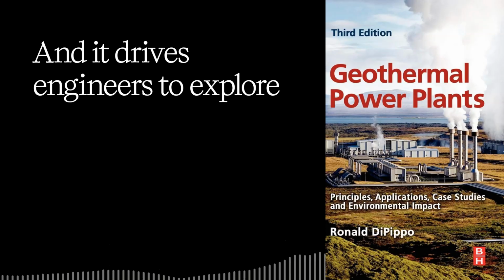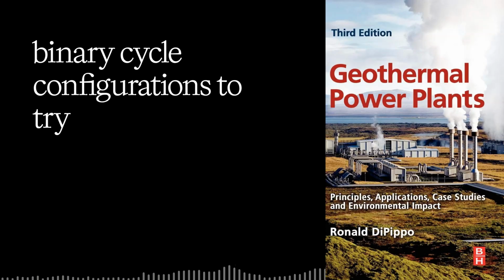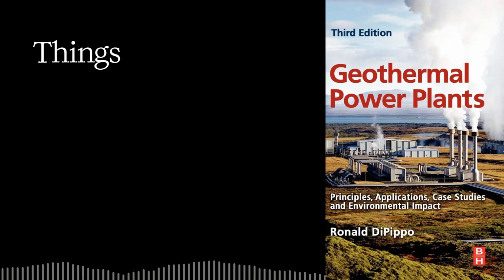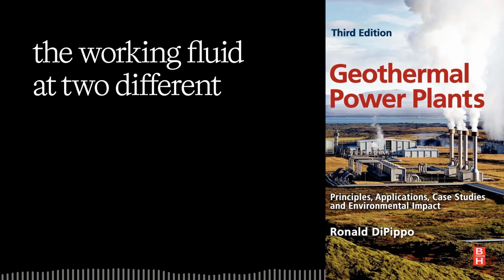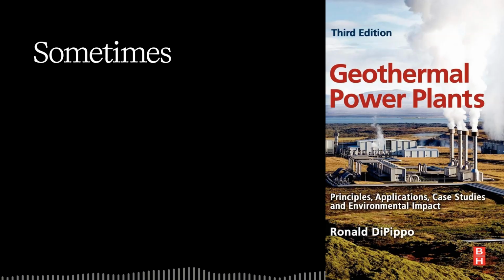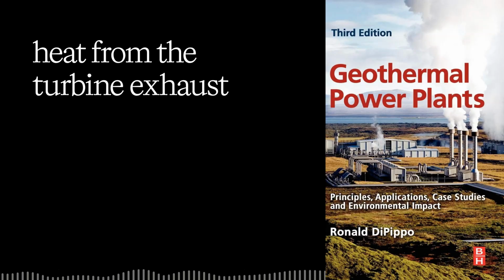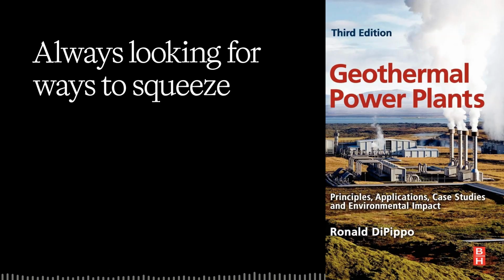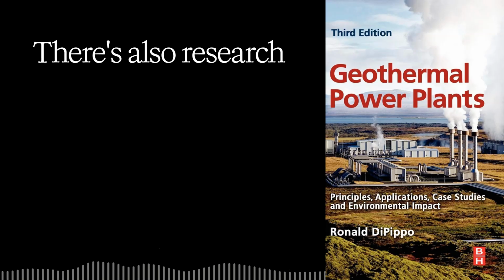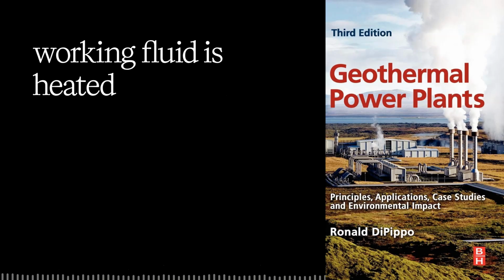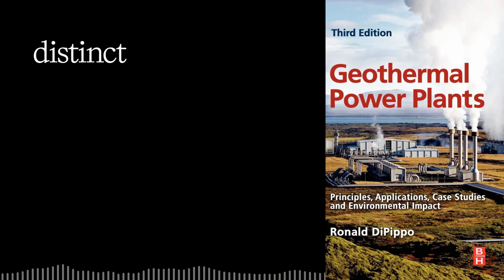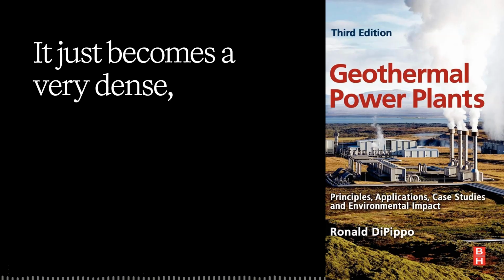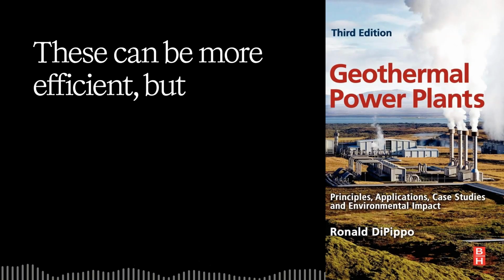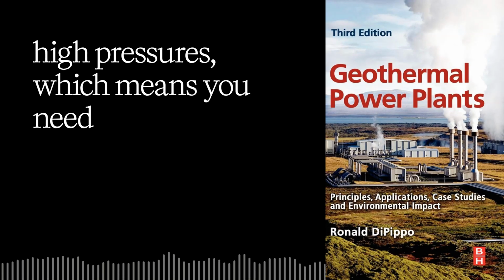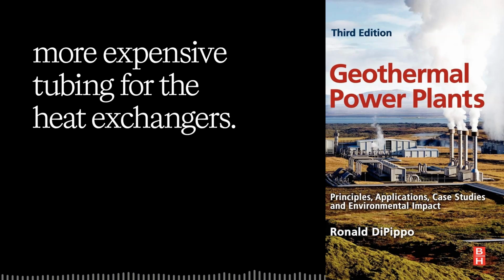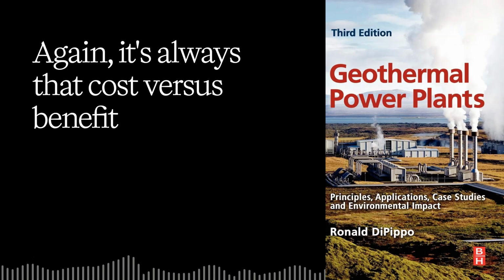And it drives engineers to explore more advanced binary cycle configurations to try and improve efficiency while managing costs. Things like dual pressure cycles, where you boil the working fluid at 2 different pressure levels, or dual fluid cycles, sometimes using a recuperator to capture waste heat from the turbine exhaust to help preheat the working fluid. Always looking for ways to squeeze out more efficiency. Always. There's also research into supercritical cycles where the working fluid is heated above its critical pressure, so it never actually undergoes a distinct boiling phase change. It just becomes a very dense, hot fluid. These can be more efficient, but they operate at extremely high pressures, which means you need much thicker, more expensive tubing for the heat exchangers. Again, it's always that cost versus benefit trade-off.